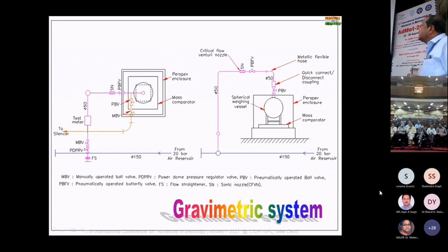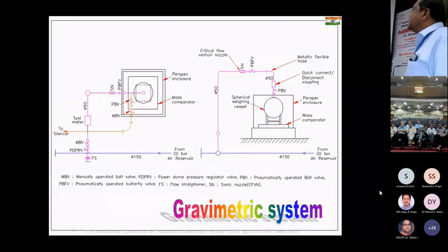So this is the gravimetric system I can explain. Air from the four cylinders is coming through a 150 mm stainless steel tube. And here we have the regulator. We adjust the pressure in the regulator manually, so whatever is the required pressure for calibration, we adjust it manually. And this is the test section where we mount the test meter. And then it goes to the vessel.